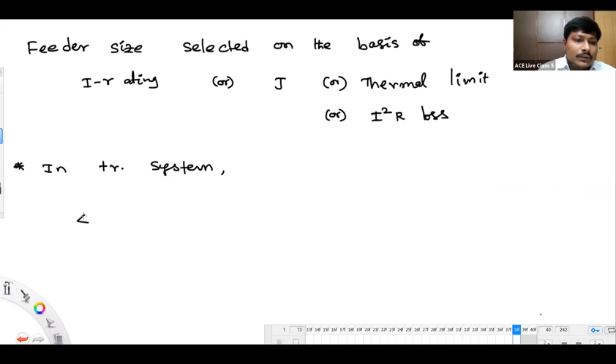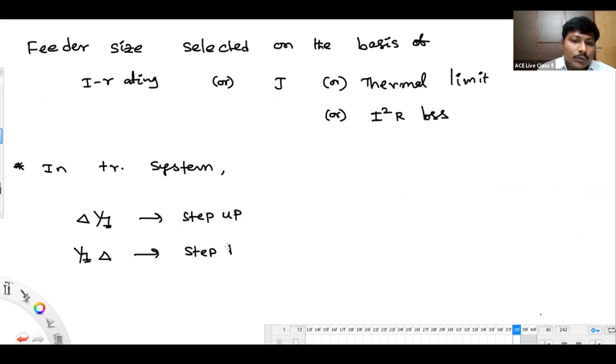Economical connection suggested for step up is delta star ground, whereas for step down, the reverse, star ground delta, is suggested, particularly in the transmission system, not in the distribution. Only in the transmission system we take up that comment. In the transmission system, delta star ground is used for step-up application. Star ground delta is used for step-down application. These are economical connections.